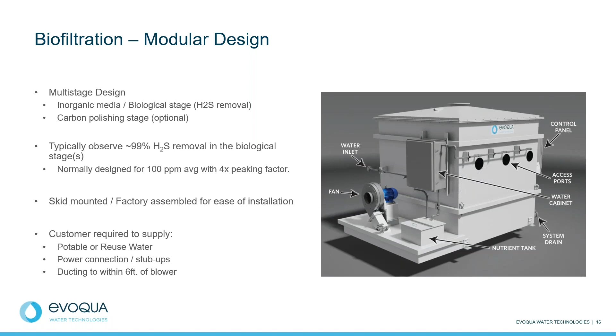Also, these systems are multi-stage in design, where the first stage is always an inorganic media that acts as that substrate for the biology to grow. And then the second stage can either be more biological media, or it can be a carbon polishing stage that can scrub any residual odors that might get through the first stage. And typically we see about 99% removal of hydrogen sulfide through the biological stages. And these systems are usually designed for 100 ppm average loading with a peaking factor of 4x, or 4 times that average.